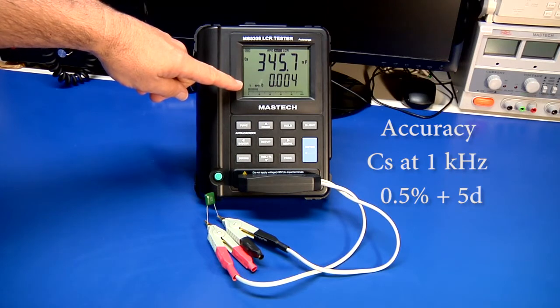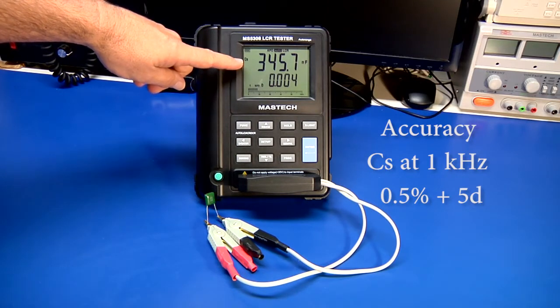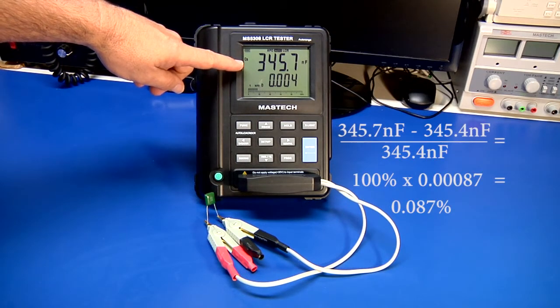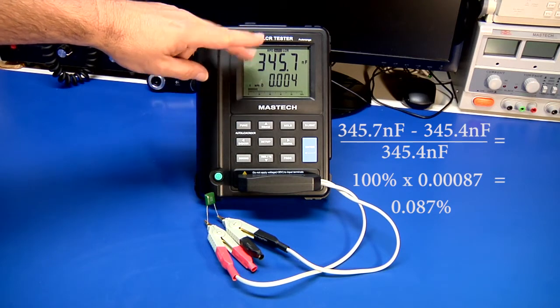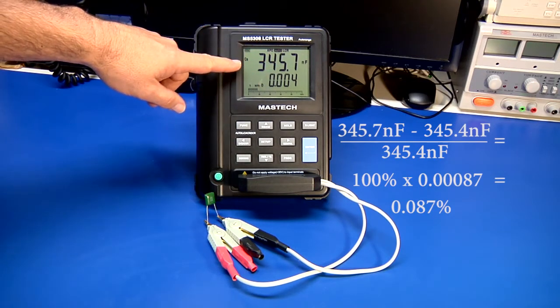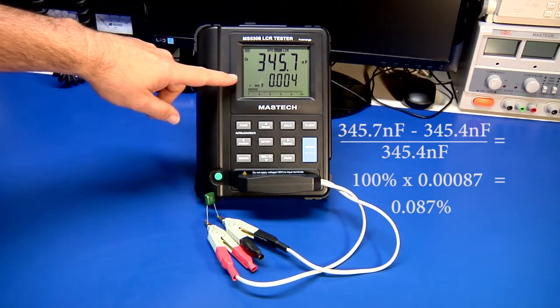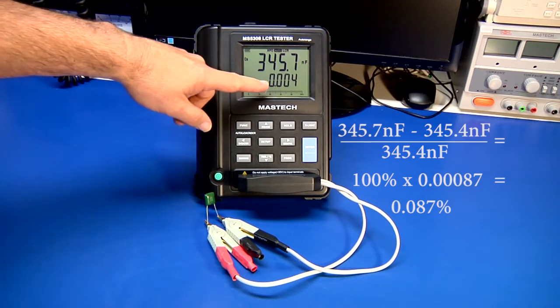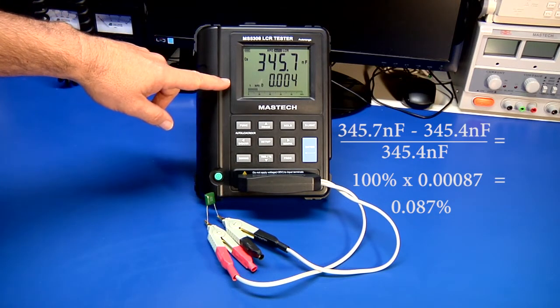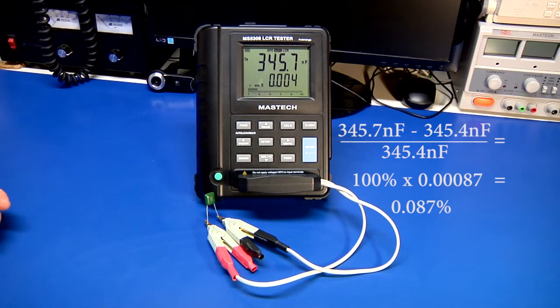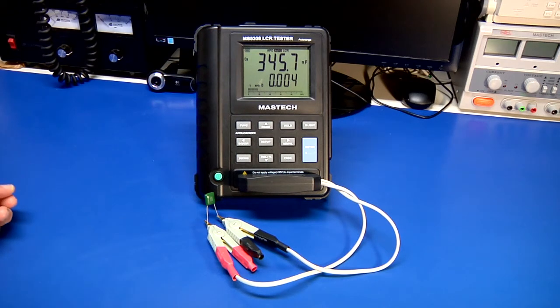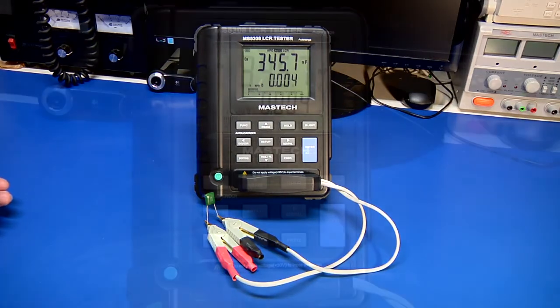According to the lab, this should be a 345.4 nanofarad capacitor, and we're reading 345.7. Again, it may toggle around the least significant digit. Their dissipation factor was 0.004, so we're reading the same dissipation factor. Again, I did 4 or 5 different capacitors and coils, and I've kind of checked it out, and everything does seem to be in spec, seems to be a pretty good reading.